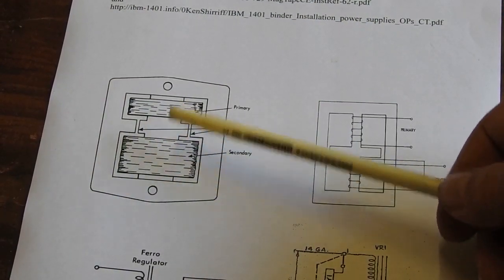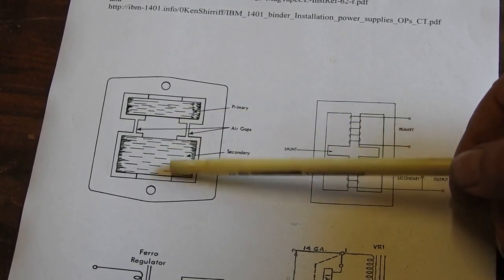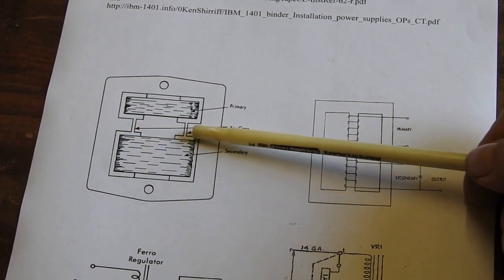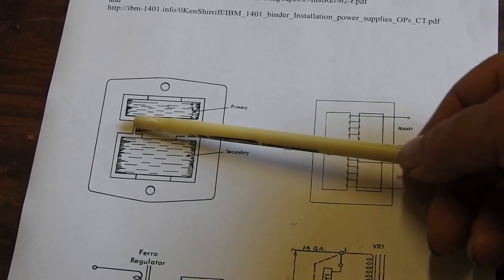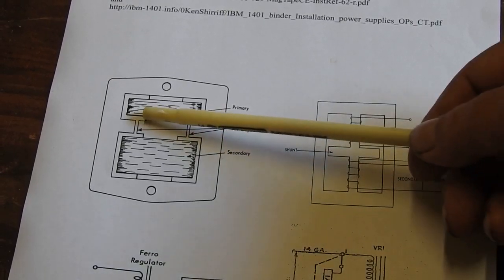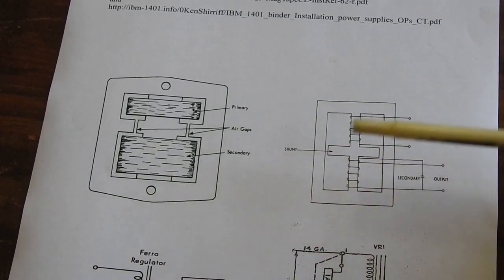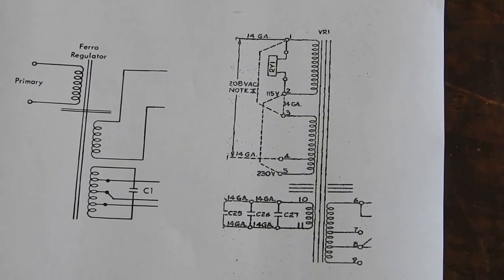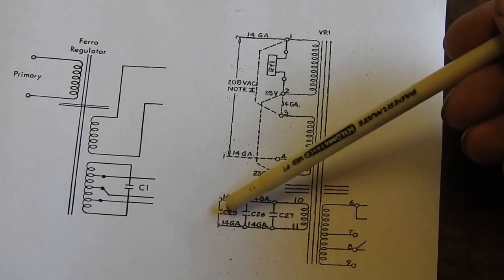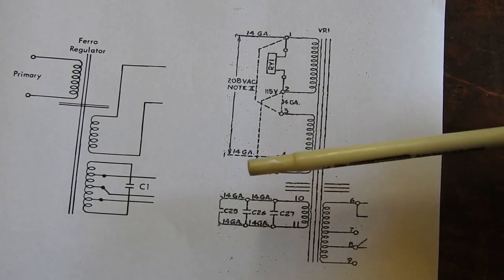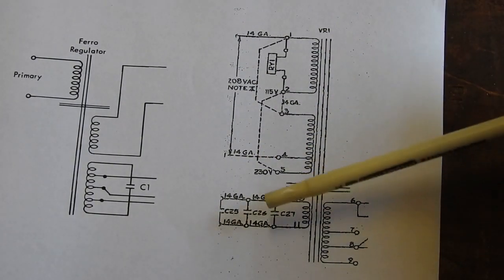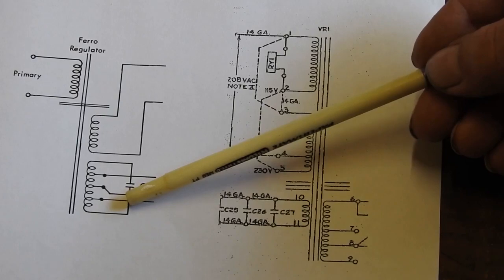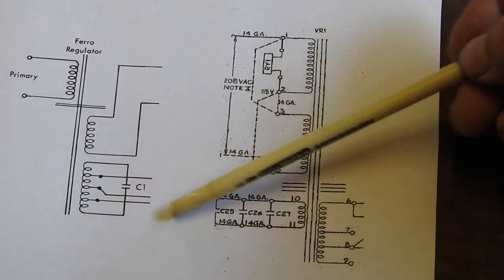Primary and secondary are usually separate. And the connection, the magnetic connection between those two parts of the magnetic circuit is lossy. Caused by a magnetic shunt, a lump of steel in between, and air gaps. Another feature is that there's a secondary winding with a capacitor across it. Such as here where we have a winding by itself with three capacitors in parallel with it. So all the ferroresonant transformers have that. But sometimes the winding is standalone like that. And sometimes it's like this where the winding is also part of the secondary providing output current.